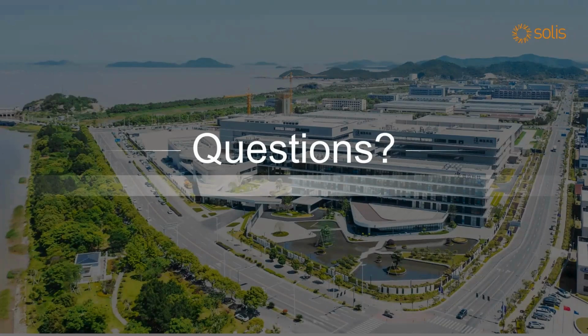Well, indeed. Whether you stay in our MPPT operating window, or better yet, you stay within our full power MPPT voltage window, I don't care. What I care about is whether or not you exceed 600 volts under any conditions. The hottest day, 1.25 sun, in Ontario, I don't care where. If you are under my ISC number, my short circuit current number, you're within warranty.